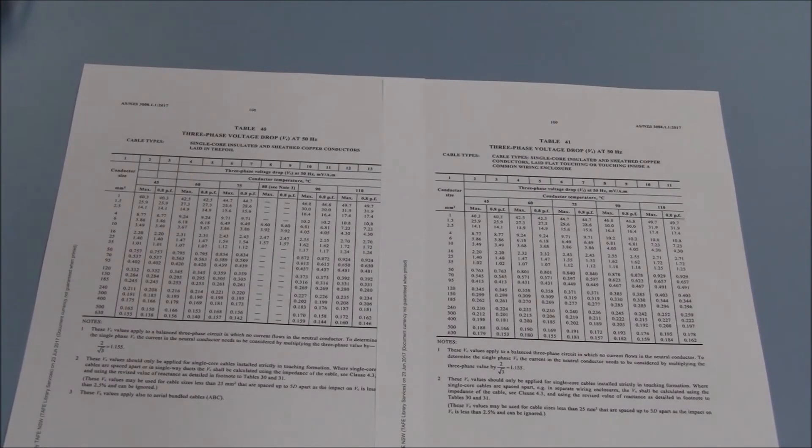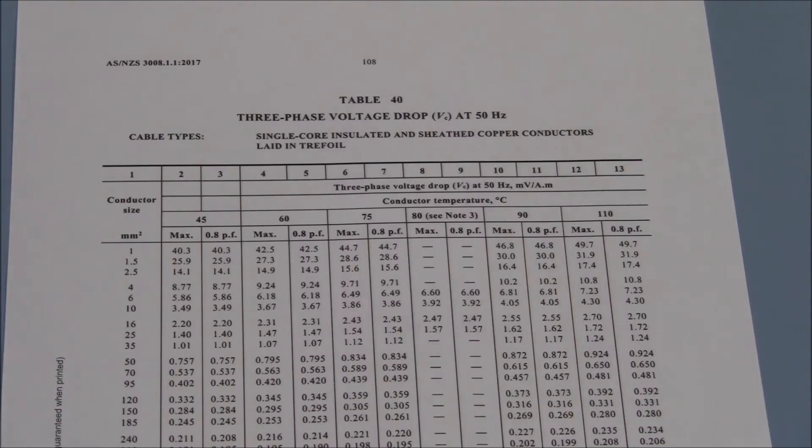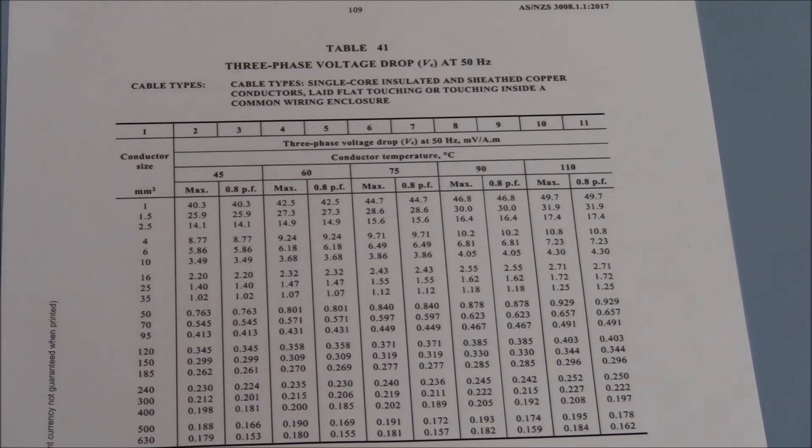Our value of VC will come from either table 40 or table 41 as they relate to copper SDIs. Table 40 is for copper SDIs installed in trefoil. Table 41 is for copper SDIs installed in any other situation or fashion, be it underground like in this example or whatever.